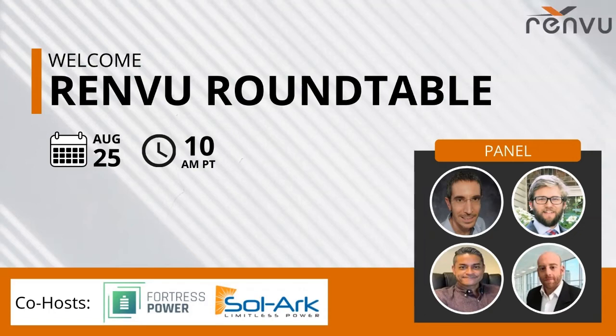I'll lead into that. I'd probably say the biggest thing we see right now is sizing the battery. That's always tricky, especially getting into ESS, especially if you've only been doing grid-tied for a while. Sizing the solar is pretty straightforward, but batteries can be concerning because depending on which you choose—Fortress with LFP or lead acid, either or—you want to make sure it's sized appropriately. So one of the things we try to provide is training and tools. On our website we have a sizing tool to help get the amount of kilowatt hours you'd need in terms of battery and inverters. It is universal—it doesn't necessarily require using SolArks. We just want to provide as much information as possible for sizing and appropriating the right system for your customers or the homeowner.